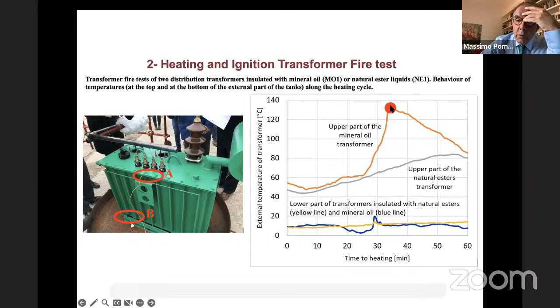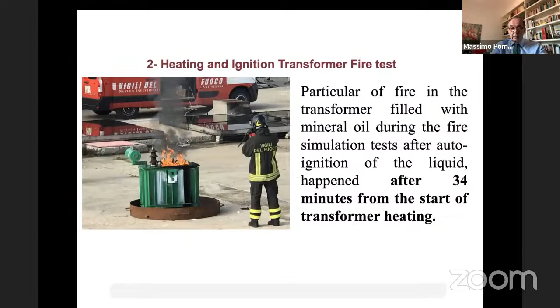In the case of orange, it's the case of mineral oil for transformer. Again, we started heating the mineral oil. The temperature increased up to 130 degrees. If you remember, this is the fire point of the mineral oil. So it means that the oil started to burn, as you can see here. We preheated the oil, and arriving at that temperature after 34 minutes, more or less half an hour, the oil started to burn.